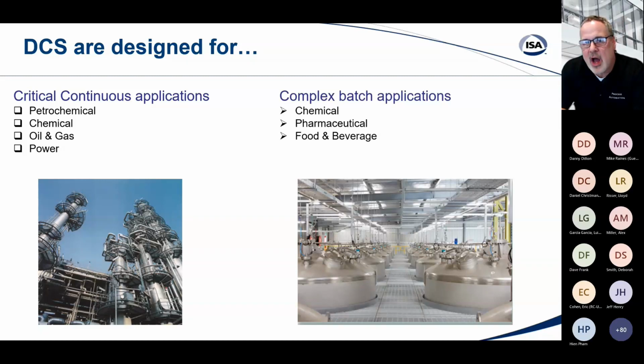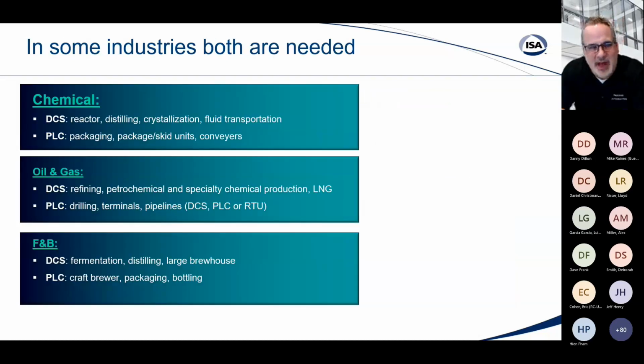On the other side, you have these complex batch applications, typically seen in the chemical, pharmaceutical, and food and beverage industries. And I say complex because this is where that crossover happens between, well, do I choose a PLC or do I need to go DCS? It really is going to depend on the complexity of the application. Oftentimes, particularly in the pharmaceutical industry, these reactors might be controlled locally by a PLC and then supervised with the DCS over top of it. So there's typically that type of mix, which brings me to my next slide.